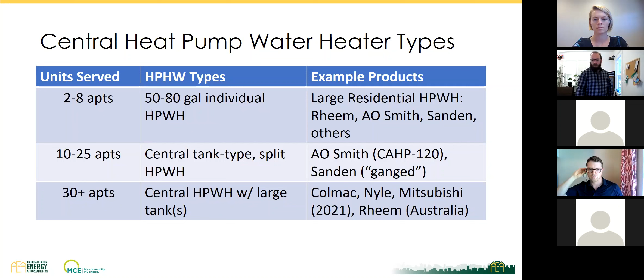So again, some more design considerations. Optimal sizing will likely have more storage than gas-based systems. That's pretty typical. The engineer should not be using the same sizing parameters as gas hot water systems. The reason you need more storage is that you might think of a typical gas water heater as using a flamethrower, and a heat pump as more of a simmer setting. So the recovery time is slower. To offset that, by having more storage that we can draw down on, we're able to provide more hot water. So the trade-off is slower recovery time, but more storage.